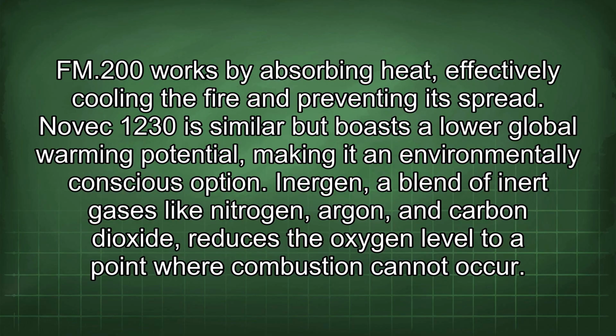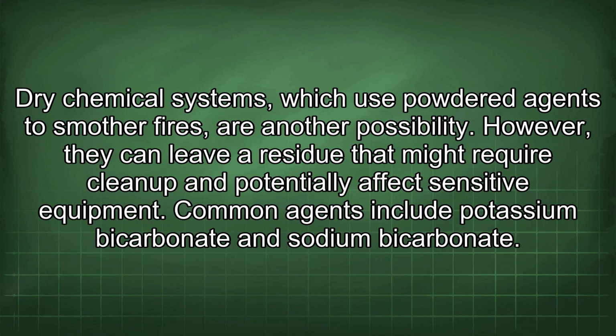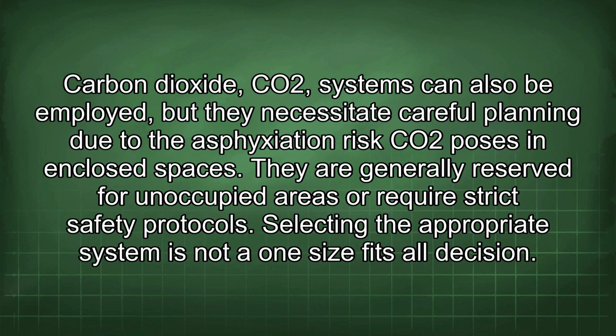Inergen, a blend of inert gases like nitrogen, argon, and carbon dioxide, reduces the oxygen level to a point where combustion cannot occur. Dry chemical systems, which use powdered agents to smother fires, are another possibility. However, they can leave a residue that might require cleanup and potentially affect sensitive equipment. Common agents include potassium bicarbonate and sodium bicarbonate. Carbon dioxide, CO2, systems can also be employed, but they necessitate careful planning due to the asphyxiation risk CO2 poses in enclosed spaces. They are generally reserved for unoccupied areas or require strict safety protocols.